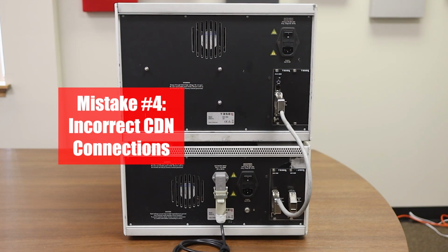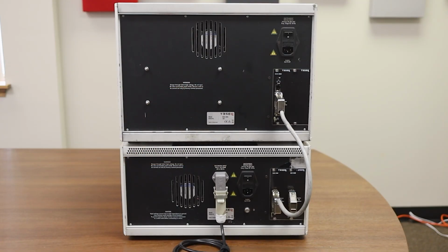Incorrect connections with the CDNs or inputs, particularly those with complex or manual CDNs, can cause serious damage to the test equipment. We've seen this occur in a few different situations where inputs have been switched or other connections have been incorrect. This can send surges back to the generator or cause other issues that can permanently damage the system.